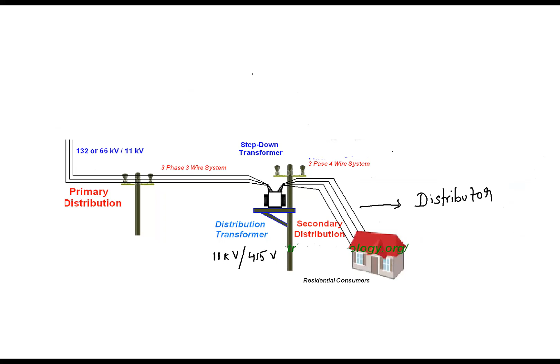Some basic idea: primary distribution usually starts at 132 kV in a very big city like Chennai. In a middle level town like Coimbatore, distribution starts at 66 kV. In a small village or small town, distribution can start at 11 kV. There is no fixed voltage - we can say this is the transmission voltage, this is the distribution voltage, but it varies from situation to situation.